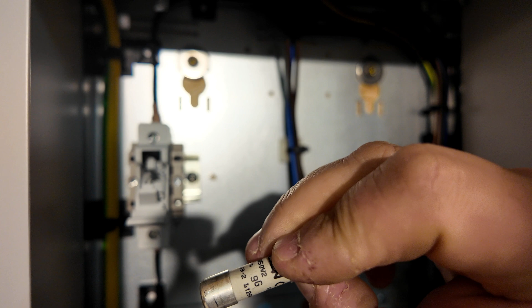If we open that up and have a little look what's inside it. So that is a 2 amp GG fuse. So that's going to sit in there and just look after the RCD element itself. Because what I'm going to do now is I'll pop you back and I will put the covers onto this and we'll liven it up. We've had everything isolated down at the main intake to this area, so none of the DBs here are energized presently. But I can get these all covered up and we can turn it on and see how it looks.